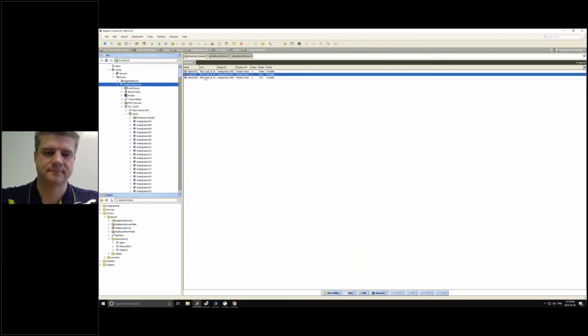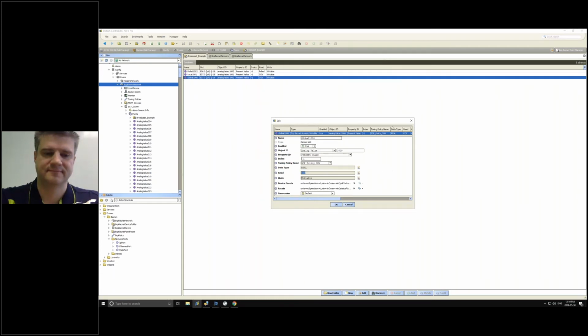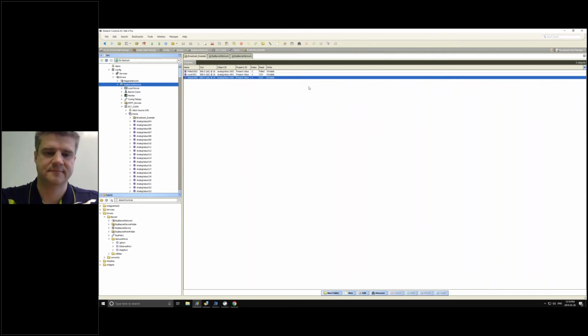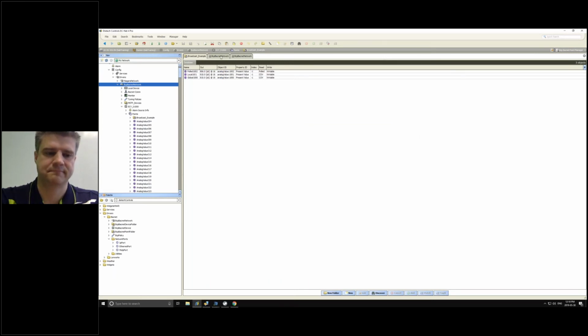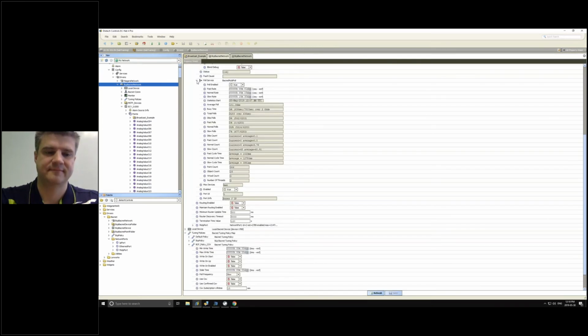But it's worth noting that because we've configured this controller by IP, when we set up VLANs, the layer 2 switches will know where that device is. It will all route, and we can get to it without having to use broadcast. So BBMD is only necessary for broadcast traffic.